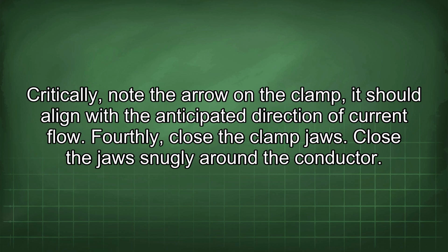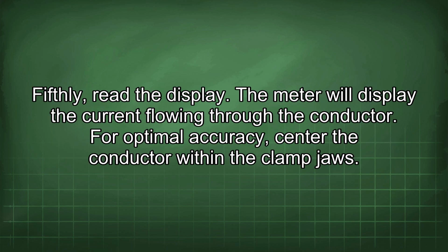Critically, note the arrow on the clamp. It should align with the anticipated direction of current flow. Fourthly, close the clamp jaws. Close the jaws snugly around the conductor. Fifthly, read the display. The meter will display the current flowing through the conductor.